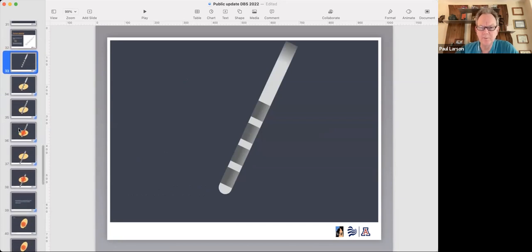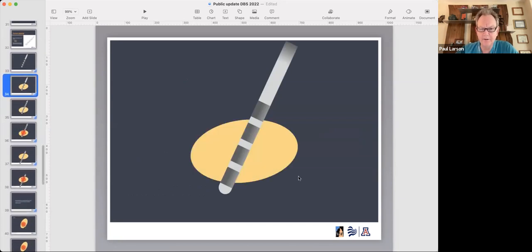So here's a DBS electrode. We're going to put it in a target. This orange thing is the brain target. And these new electrodes have gone from having 4 stimulating surfaces to having multiple stimulating surfaces. In one example, an electrode made by Boston Scientific, they actually have 8 electrodes along their stimulation DBS system instead of just 4. And they're spread over a wider area.